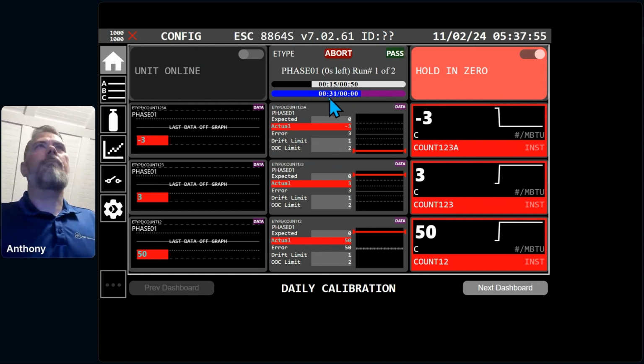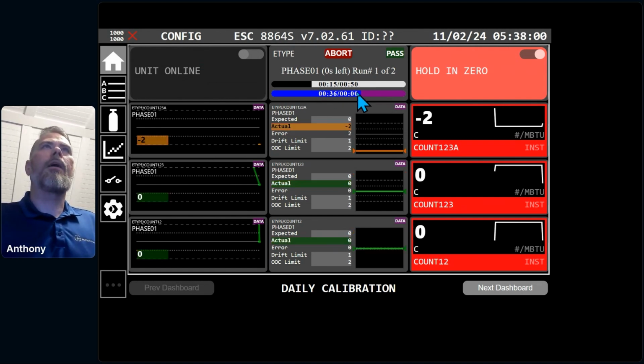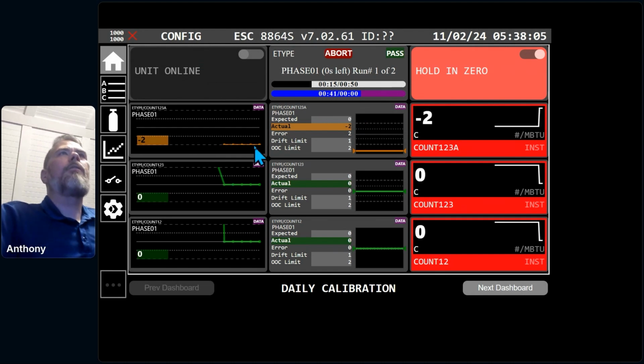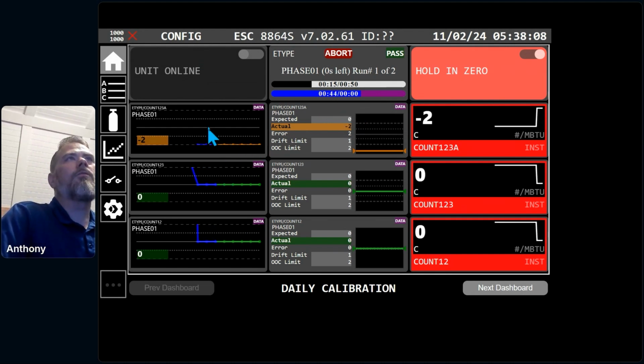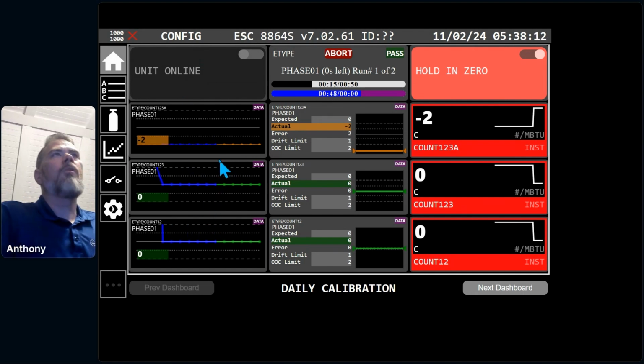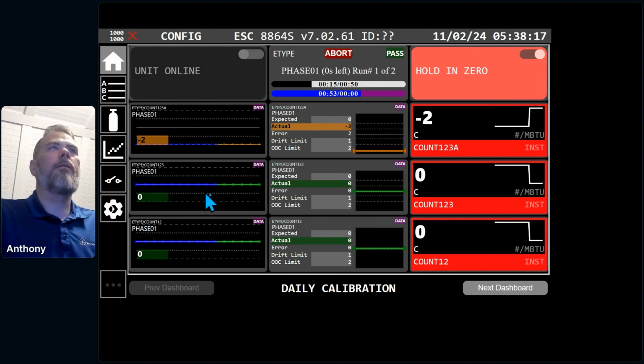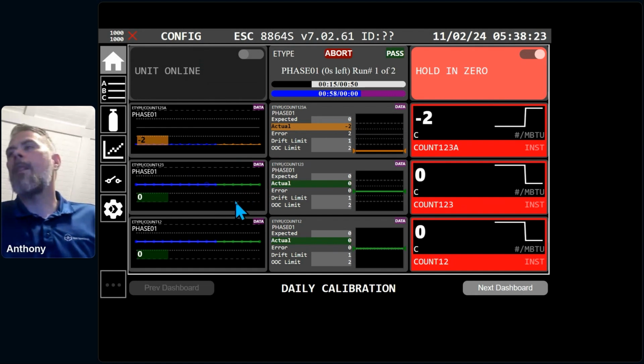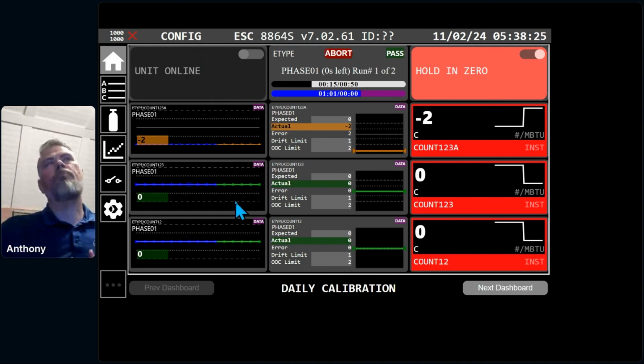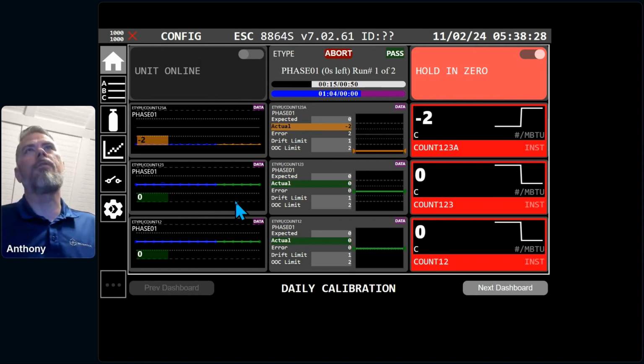You can see that our counters have stopped counting. This continues to count up, but there is no time left in the phase. This is the configured time of the calibration run. Instrument control cals work in a very similar way. Now you can see that we're starting to take on more data points since we're within the range. We were taking on data points before, but they were outside the scale. You can see that the data points that don't factor in are over here in the blue. We only color code per status the data points that are going to count towards your result. And so this ability to hold in a phase and tell you where you want to be can be very useful for tuning and other things like that.